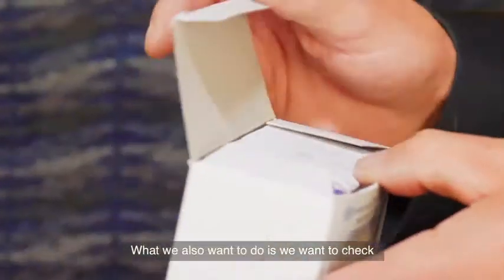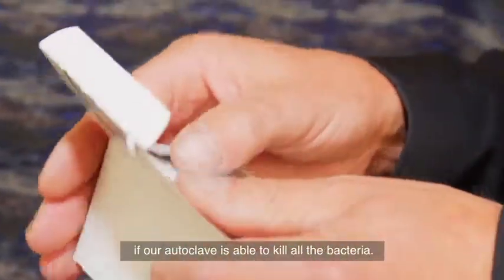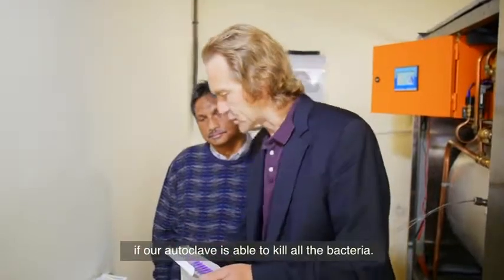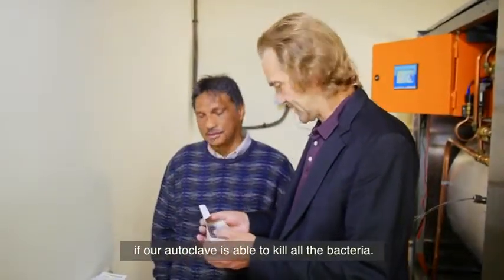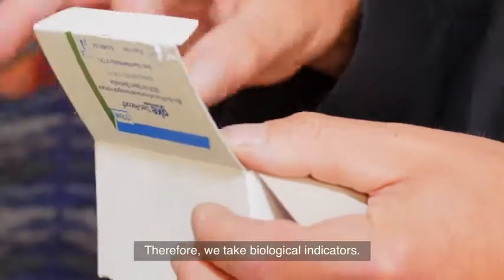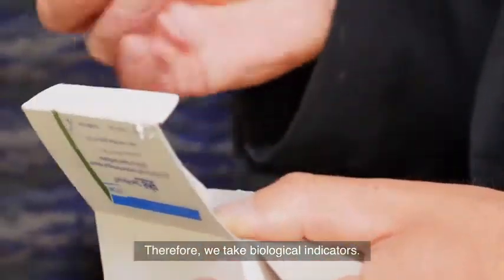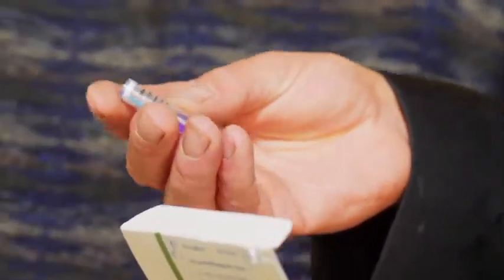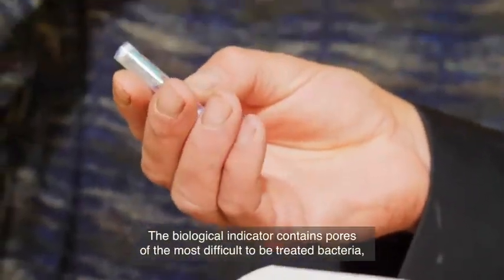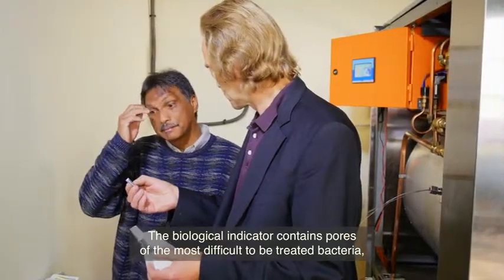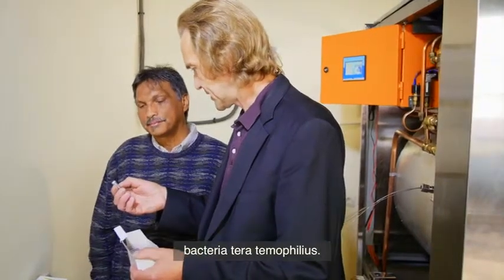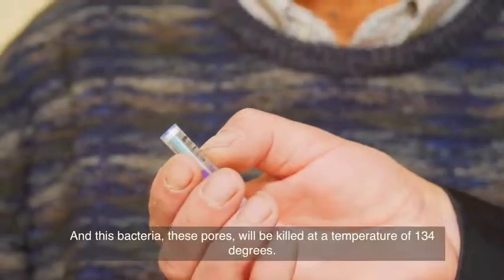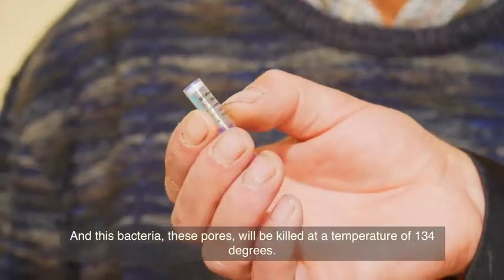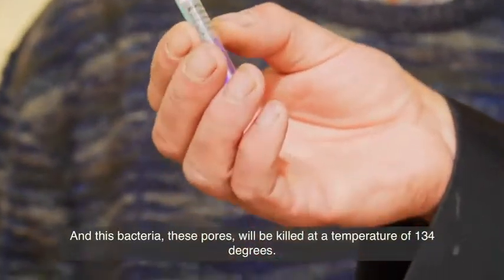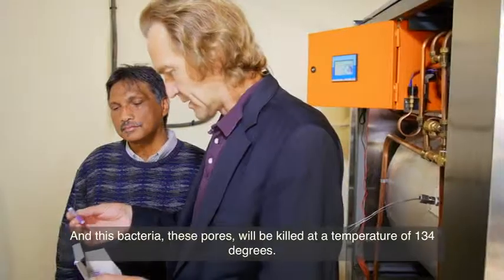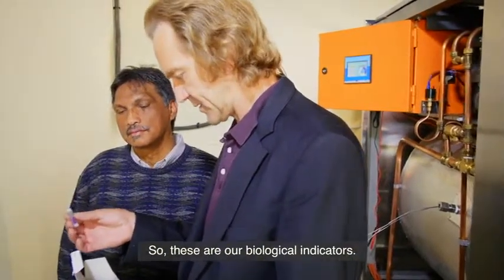What we also want to do is check if our autoclave is able to kill all the bacteria. Therefore, we take biological indicators. The biological indicators contain spores of the most difficult to be treated bacteria, Geobacillus stearothermophilus. And the spores will be killed at a temperature of 134 degrees. So these are our biological indicators.